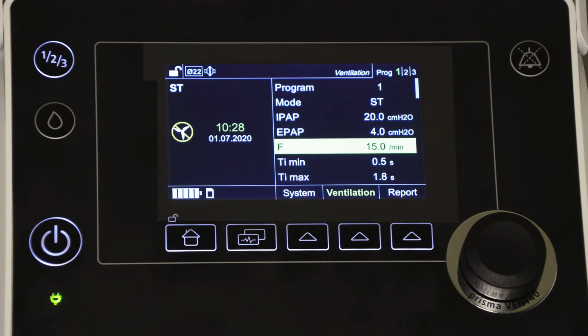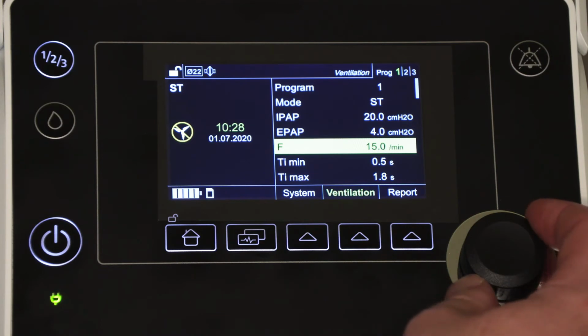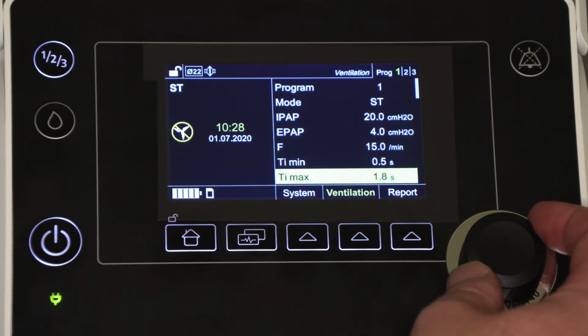The S in ST mode means spontaneous, so once the user's respiratory rate is higher than the set backup frequency, the ventilator will follow the spontaneous inspiratory and expiratory efforts of the patient by delivering the IPAP and EPAP when the patient triggers these settings. The patient can control how long each inspiration from the ventilator will be. However, if you wish to have more influence over the inspiration time allowed, the TI min and TI max settings can be adjusted to reflect this.